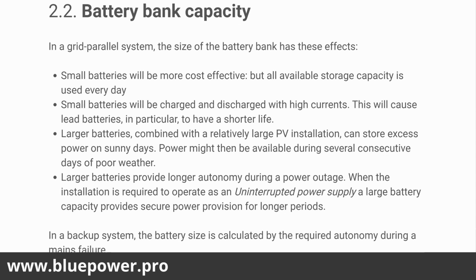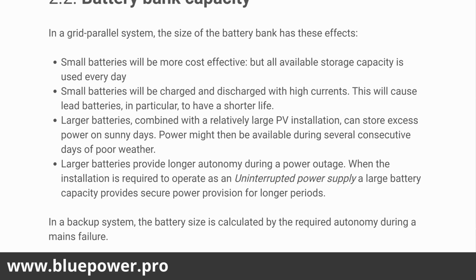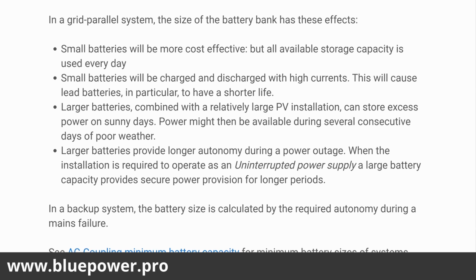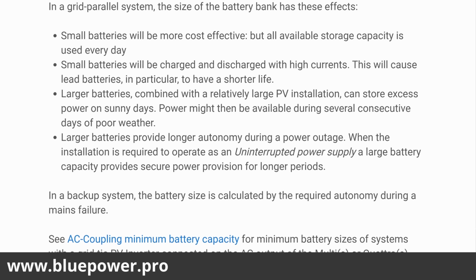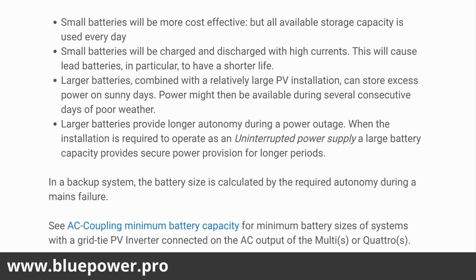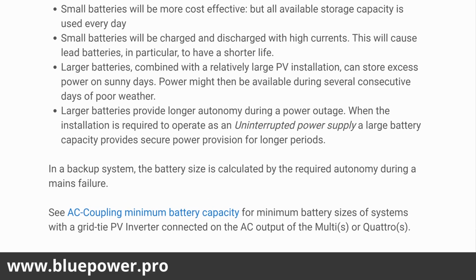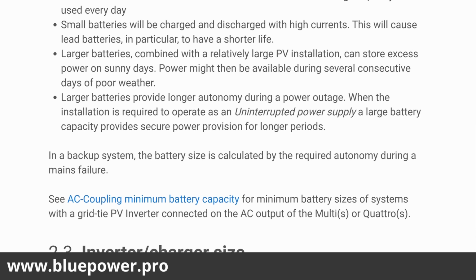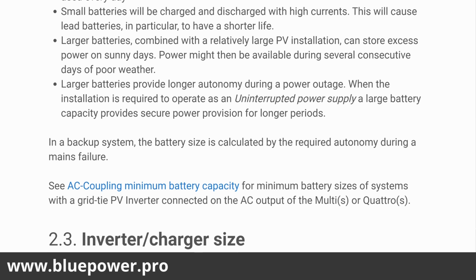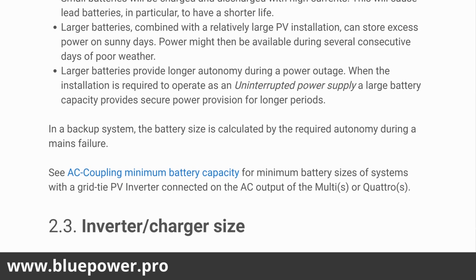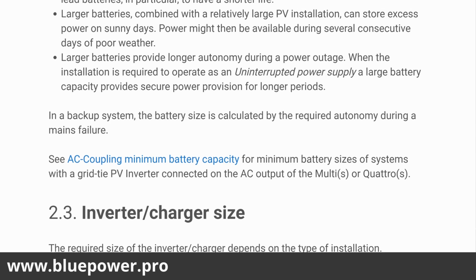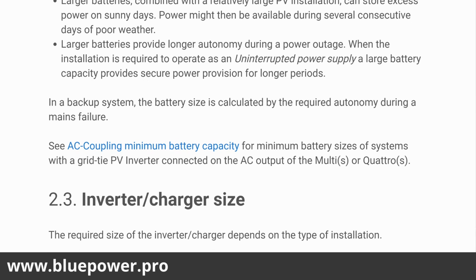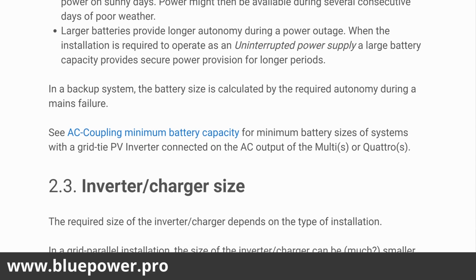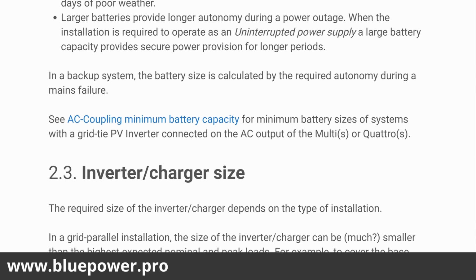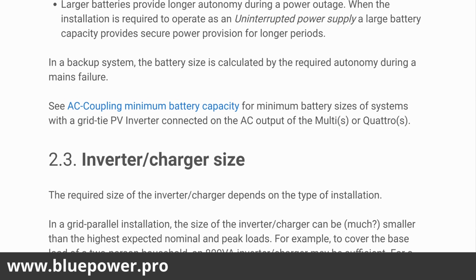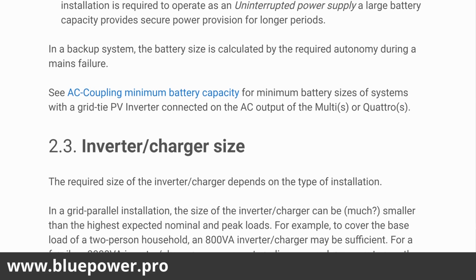So battery bank capacity. In a grid parallel system, the size of the battery bank has these effects. So small batteries will be more cost effective, but all available storage capacity is used every day. So small batteries will be charged and discharged with high currents. This will cause lead batteries in particular to have a shorter lifetime. Larger batteries combined with a relatively large PV installation can store excess power on sunny days. Power might then be available during several consecutive days of poor weather. Larger batteries provide longer autonomy during a power outage when the installation is required to operate as a UPS. The large battery capacity provides secure power provision for longer periods.